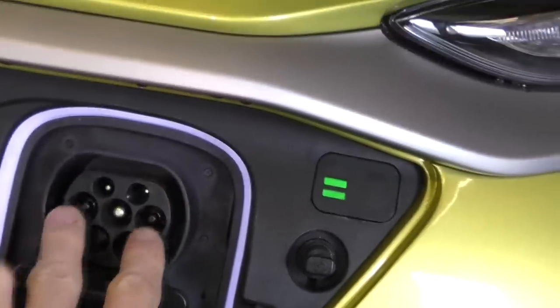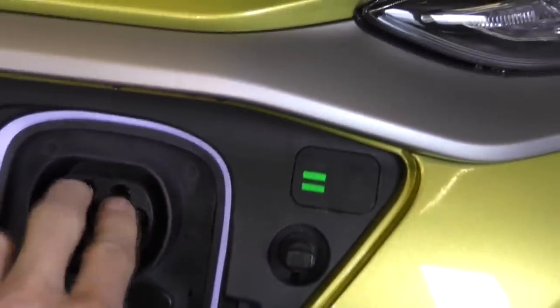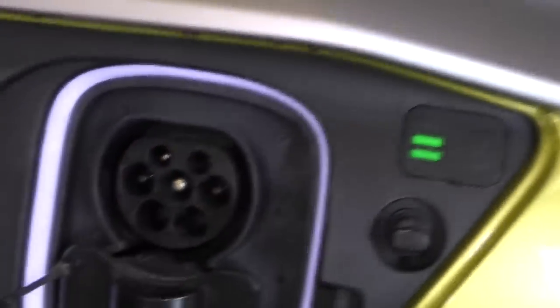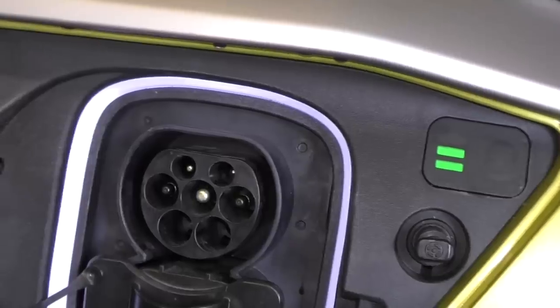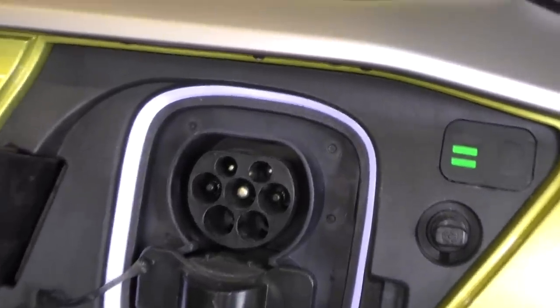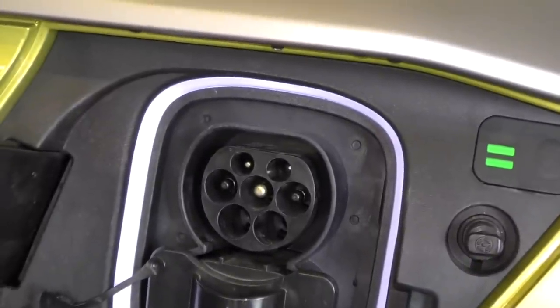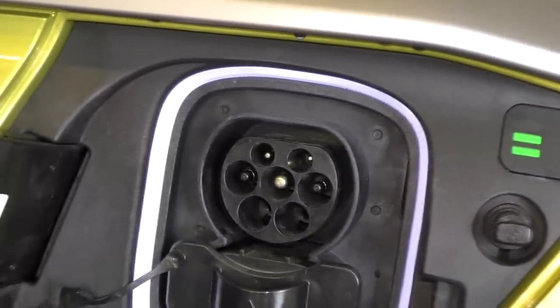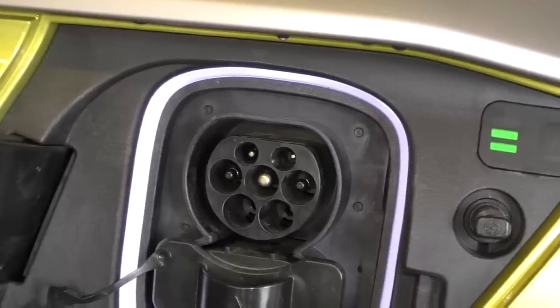This has got a couple of different sections. We've got the top section, which is for AC charging, and we've got an earth pin at the centre, 2 pins for the main supply and 2 control pins, and you can probably just about see one of those pins is recessed, so that's guaranteed to be the last one that connects, to make sure that all the other connections are made before the control signal can decide to switch anything on or off.